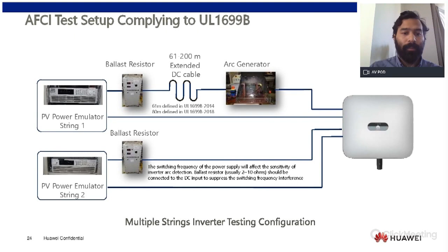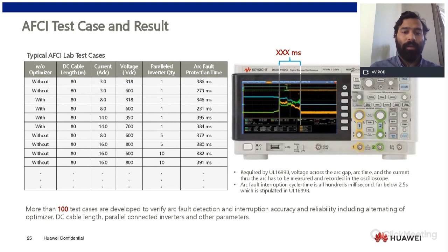As you can see here, we have tested the cases with optimizers and without optimizers, with different parallel inverters, because as I mentioned before, there could be some common mode noise between the inverters. The reaction of the arc fault detection is very, very fast, in the range of milliseconds, 200 to 300 milliseconds. We did over 100 test cases, and in 100% of them we accurately detected the fault.